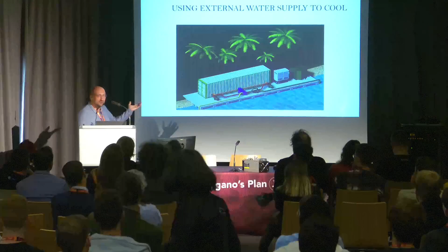Now I want to talk about the most critical inventions we made to accomplish this project. On the left side you see a typical air-cooled miner - air passes through at, for example, 30 degrees outside and is heated up to 60 degrees. On the right side is a specially designed miner for liquid cooling. The biggest difference is that liquid enters that miner already at 60 degrees and exits at only 65.